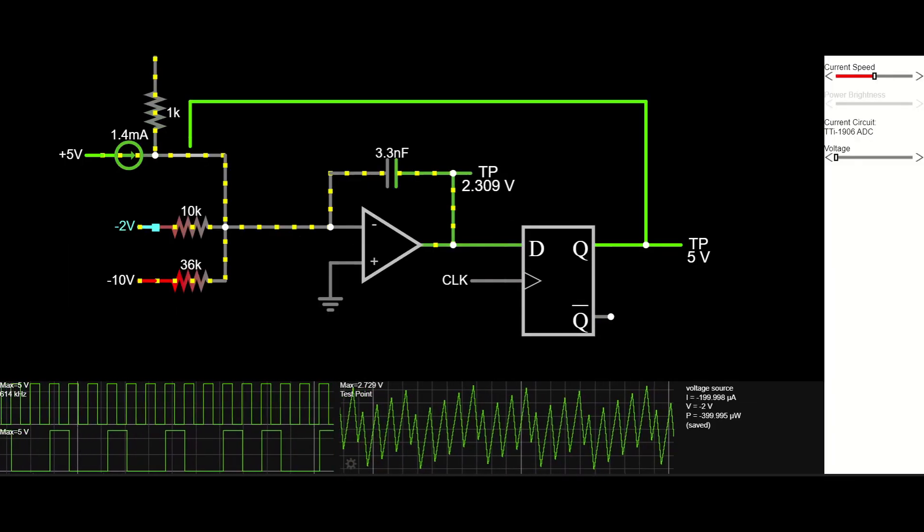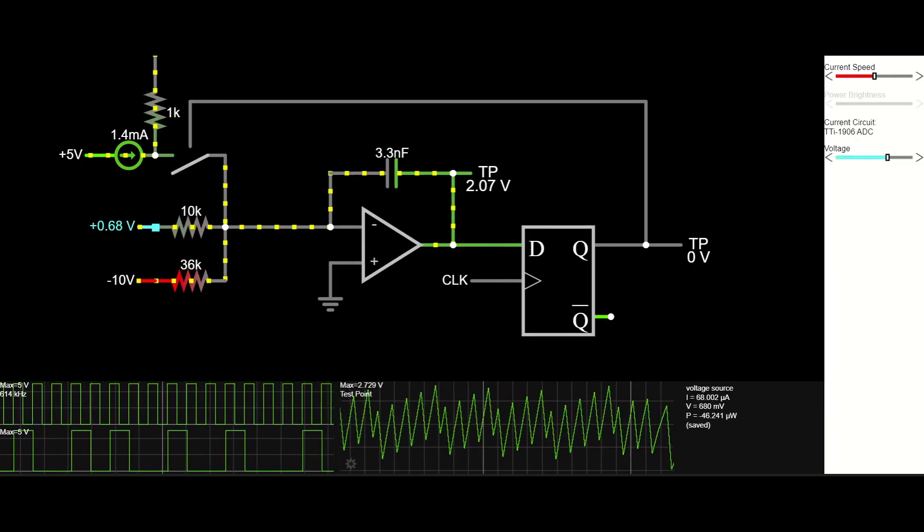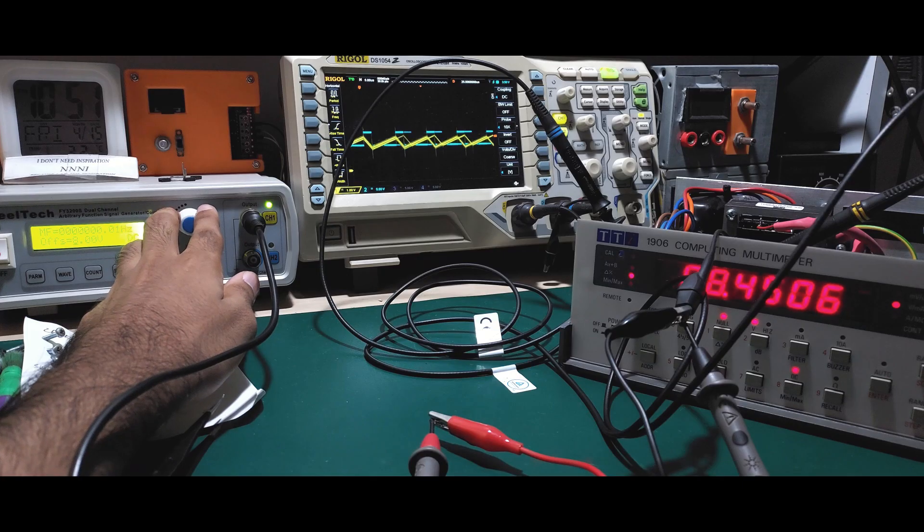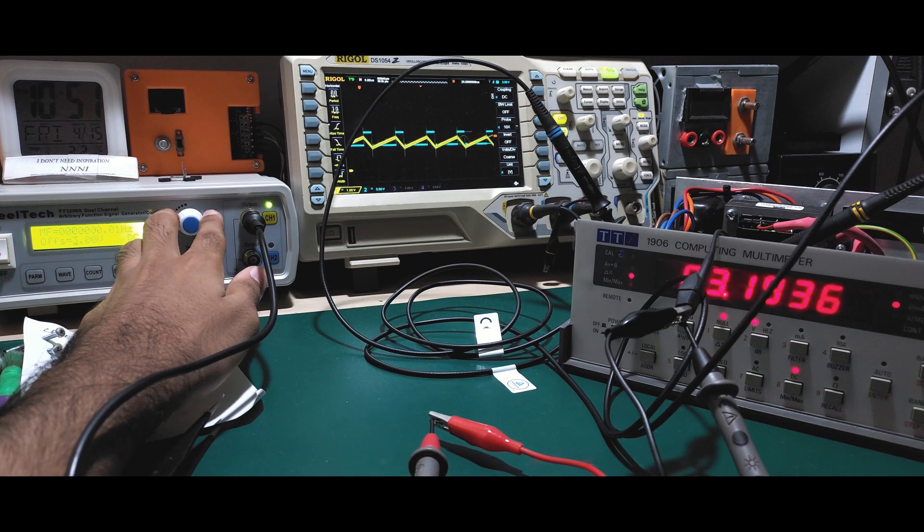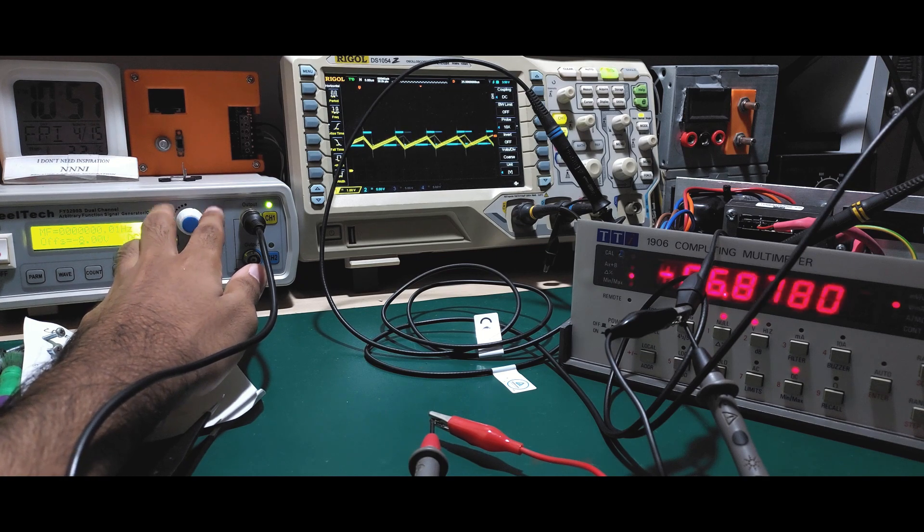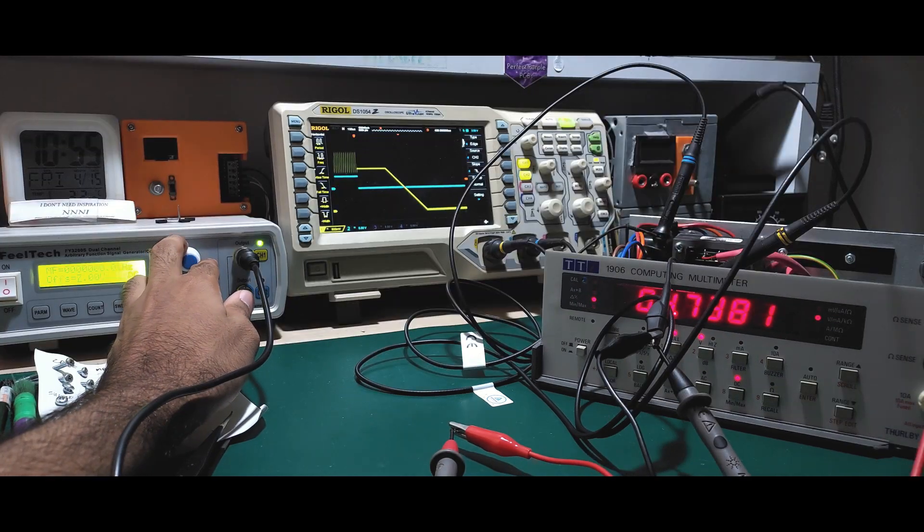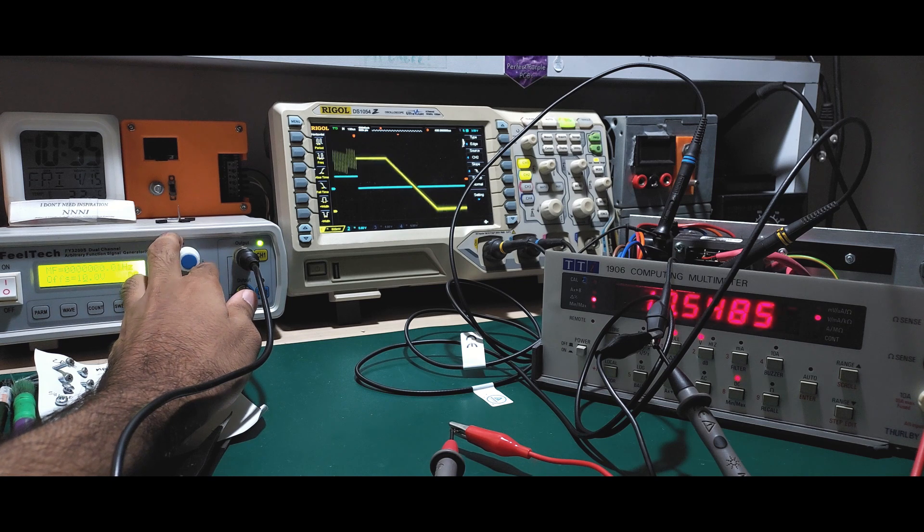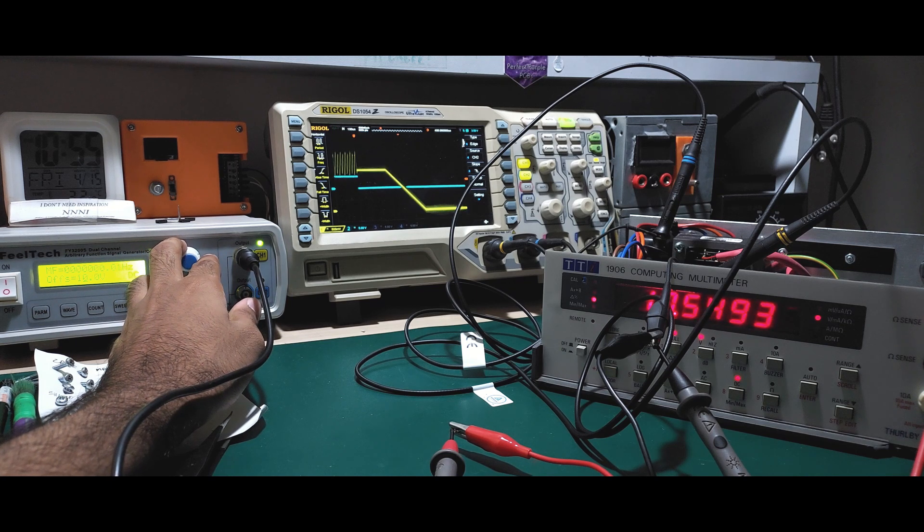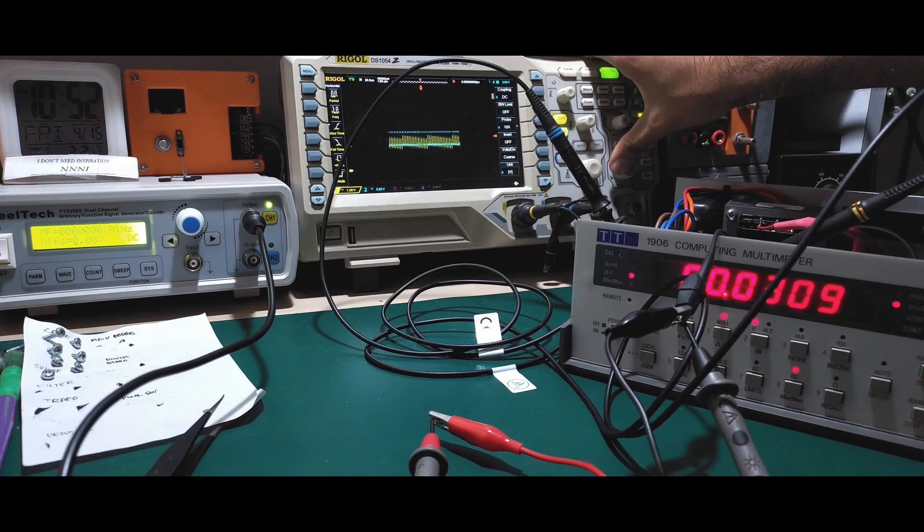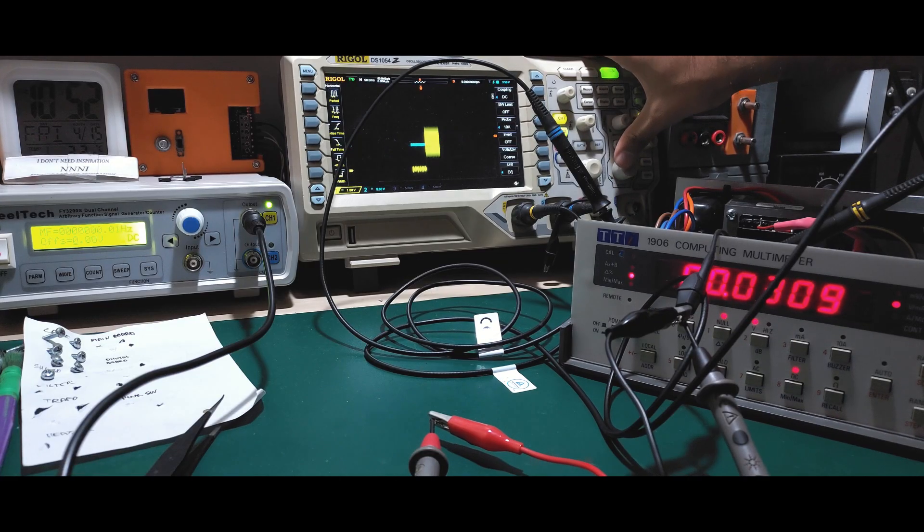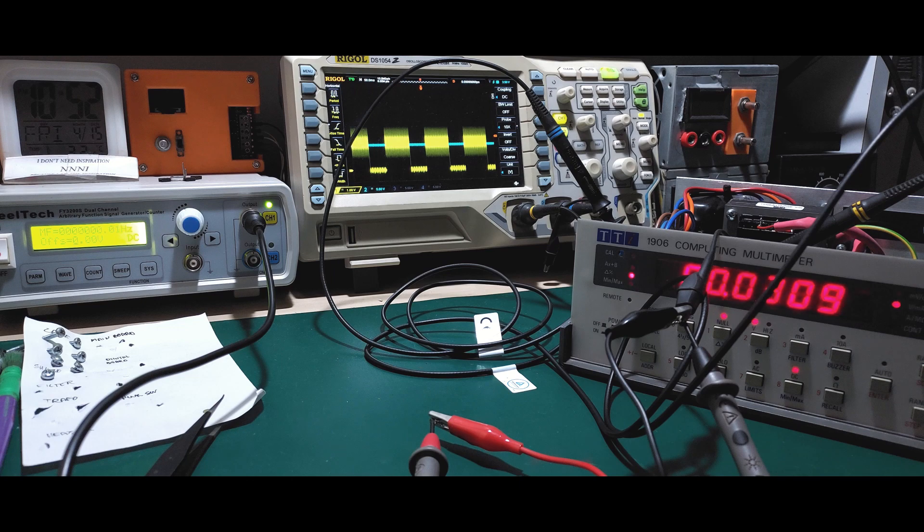The end result is some kind of voltage to frequency converter. The ADC outputs pulses of constant width, called CB pulses. The frequency of pulses is proportional to the input voltage. The ADC also measures residue by ramping down from wherever the integrator left off to analog ground and measuring the clock cycles it takes to do so. For 4.5 and 5.5 digits, the ADC integrates over 20ms and 100ms respectively.